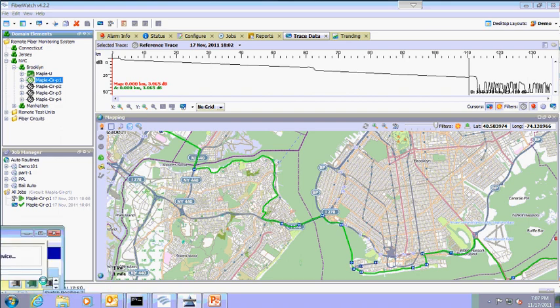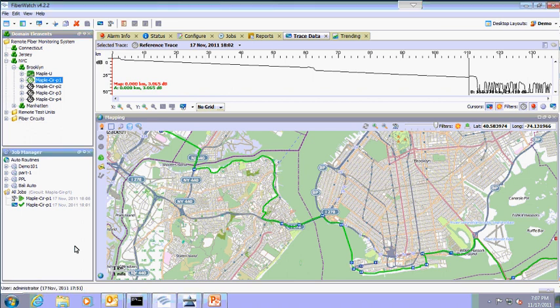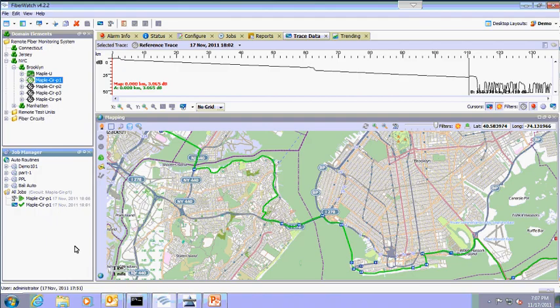You will notice that our trace is currently black. This means that this is the reference trace. The FiberWatch system is currently comparing the real-time trace to the reference trace, which takes about 10 seconds for a 100-kilometer fiber. Once a deviation is found, the system will run a more advanced measurement so that the location can precisely pinpoint the optical distance within one meter of the break.